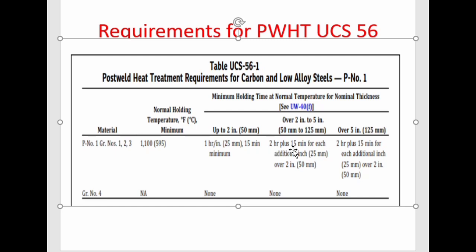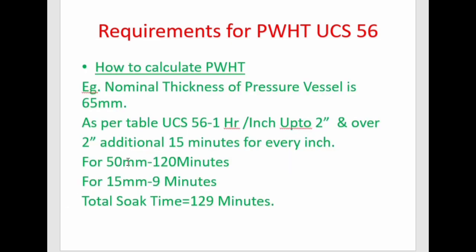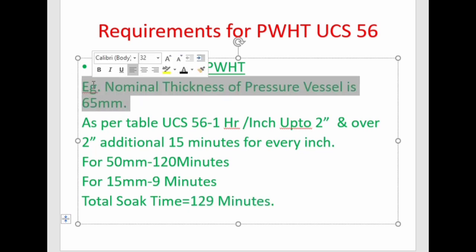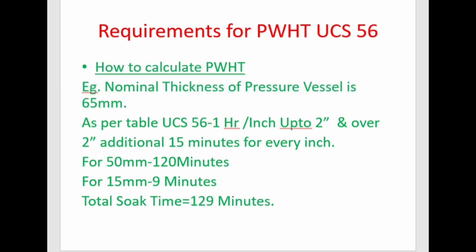Since our material is greater than 2 inches, it must be soaked for 2 hours (120 minutes) plus 15 minutes for each additional inch over 2 inches. For 65 mm, the additional thickness beyond 50 mm is 15 mm (approximately 0.6 inches), contributing an additional 9 minutes. Therefore, the total soaking time period is approximately 129 minutes for a 65 mm base plate.